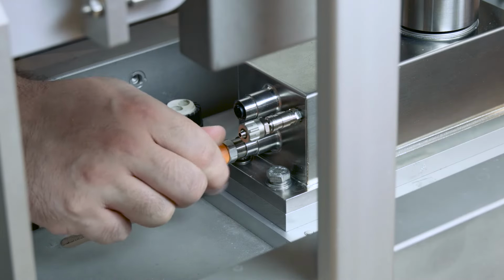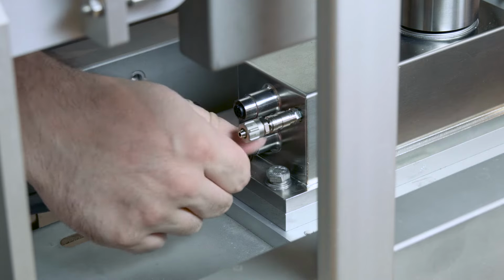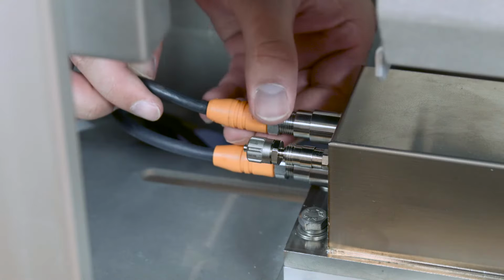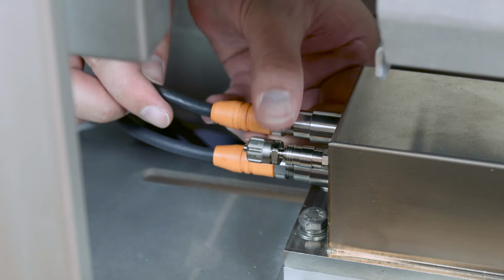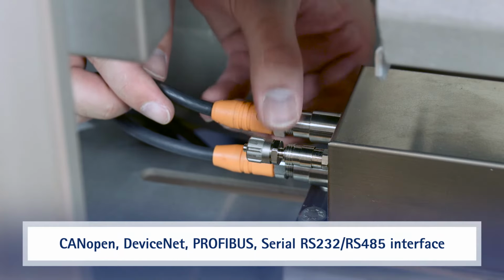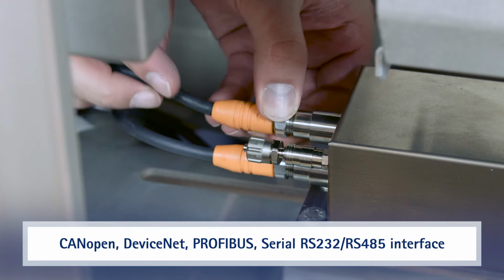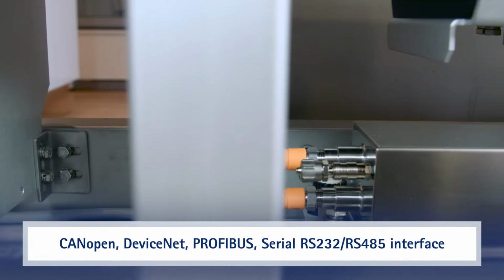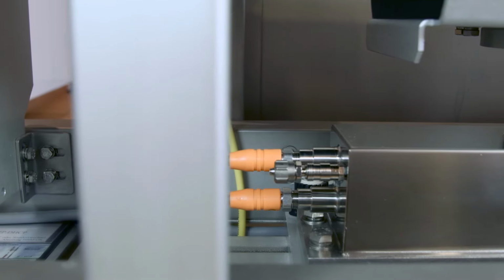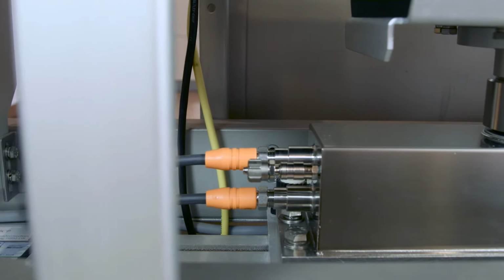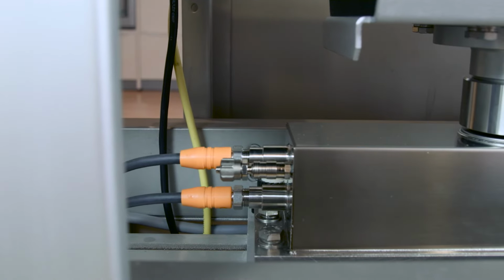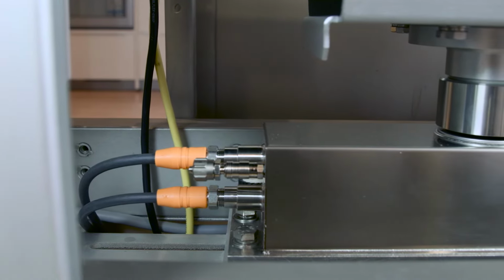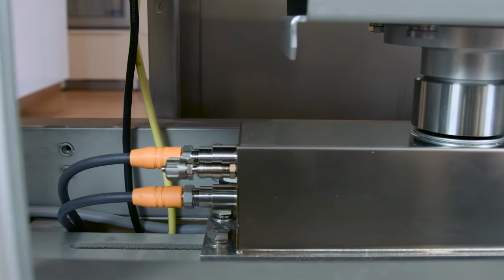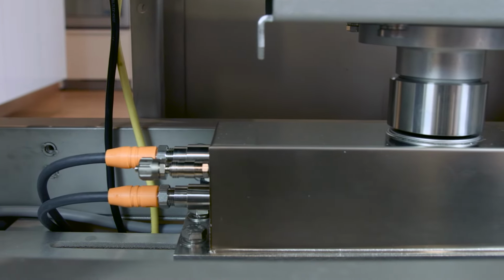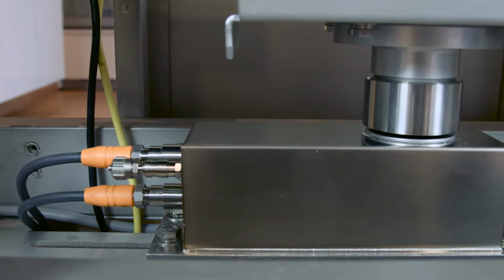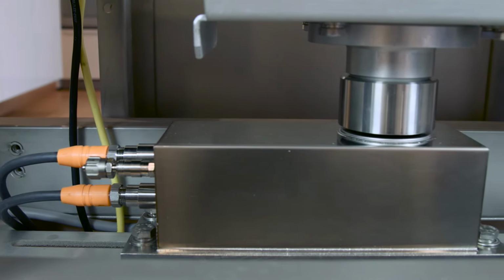Once the load cell has been integrated in the Checkweigher, we will connect the voltage supply cable and the communication cable to Fit7A. Fit7A sensor electronics support communication via CANopen, DeviceNet, Profibus, and the serial interfaces RS232 and RS485. We've selected the RS232 and RS485 interface in our example for easy communication via laptop and USB adapter. A command set with more than 100 read-write commands and multiple parameters each for the communication with Fit7A is provided.